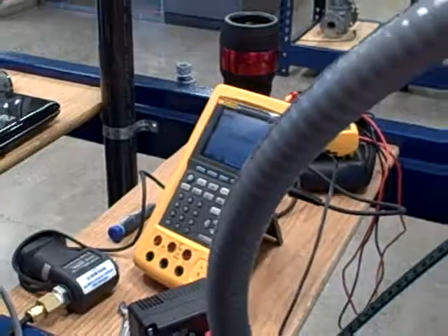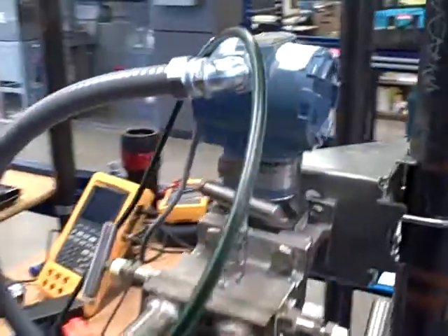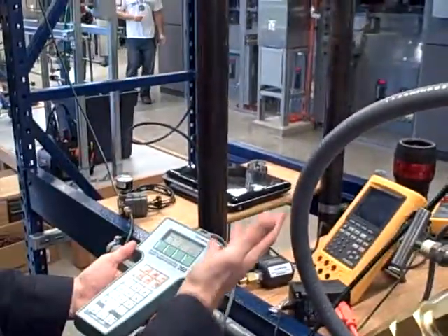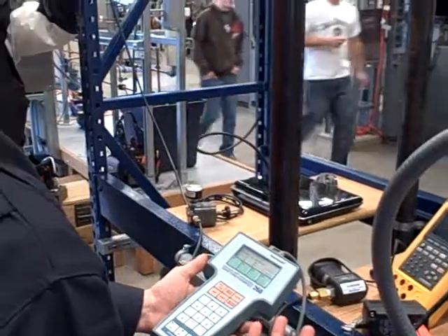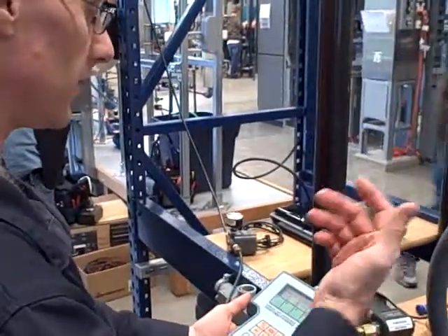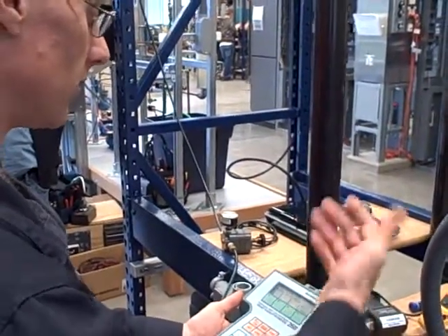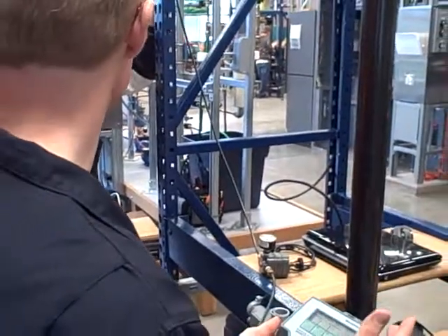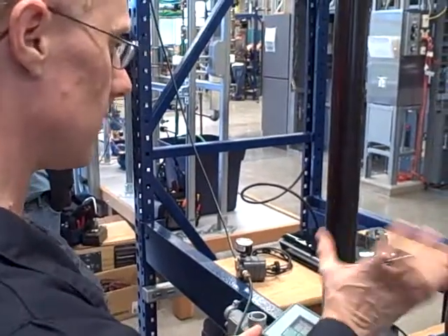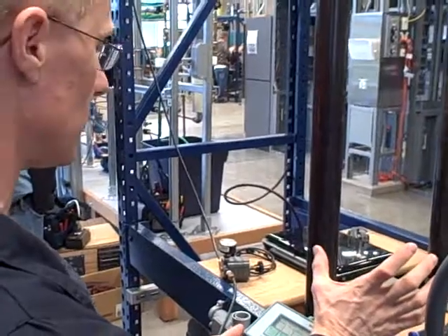What we've done is we've corrected what it thinks it sees. We've corrected the actual pressure to the perceived pressure at the sensor. The range points is a whole other step. At this point, you can range this to any range you desire. You can tell, I want it to be a 0 to 12 psi, or 0 to 20, or 0 to 25, or 5 to 15, or whatever you want. Any points within that trim range that you want on the sensor.